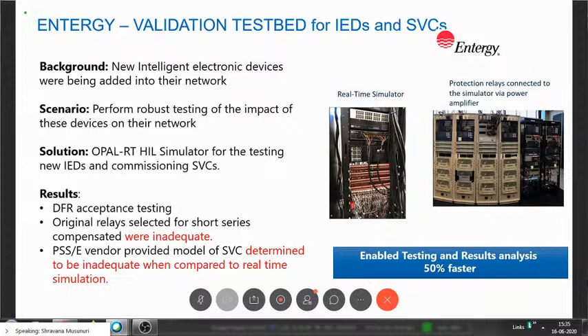Now what I'm showing is from Entergy, a utility in the United States. The background is that almost a decade back or earlier, they had multiple intelligent electronic devices being added into the network. The vendor had already tested them, but they wanted to perform more robust testing of the impact of these IEDs and SVCs, the static var compensators, on their network, to make sure that what is being shown will really impact their actual utility network positively.